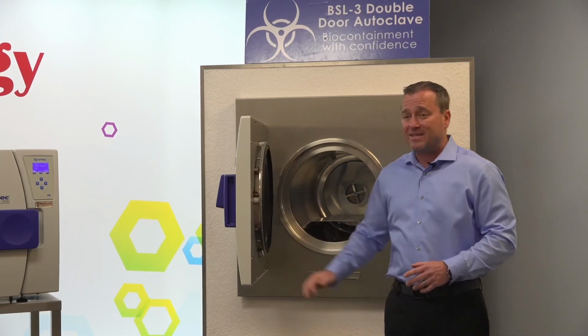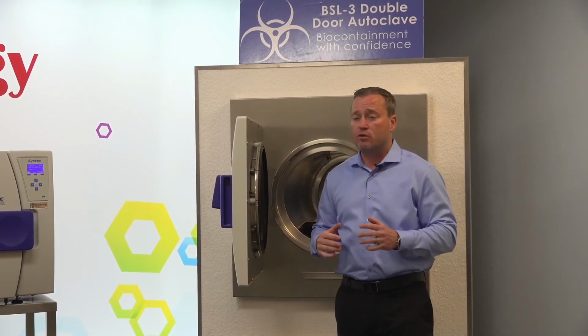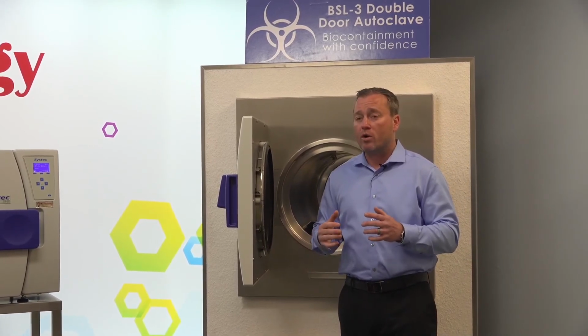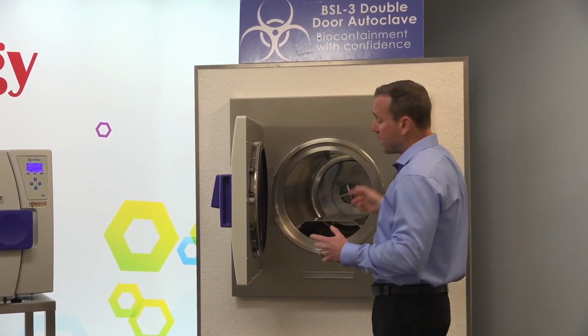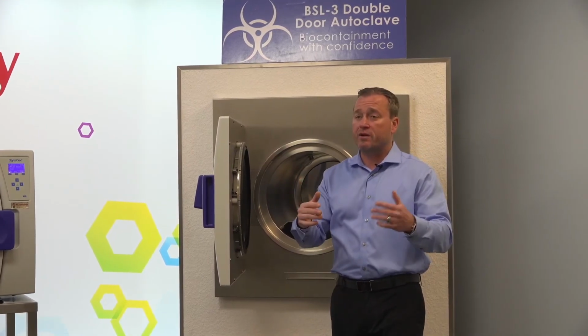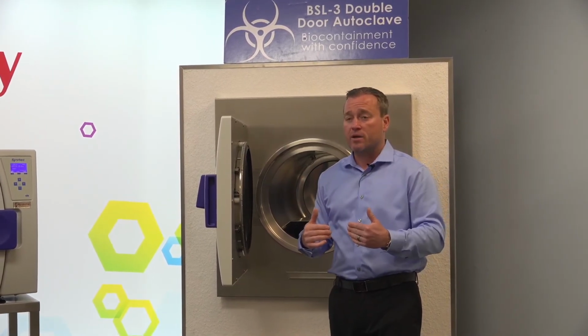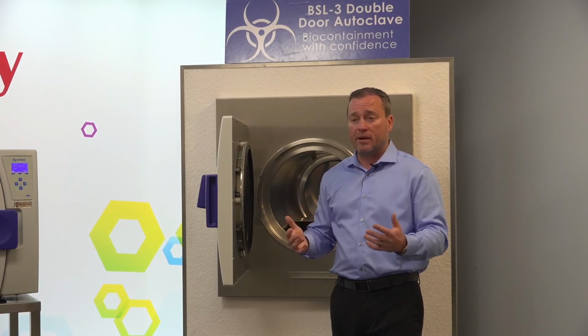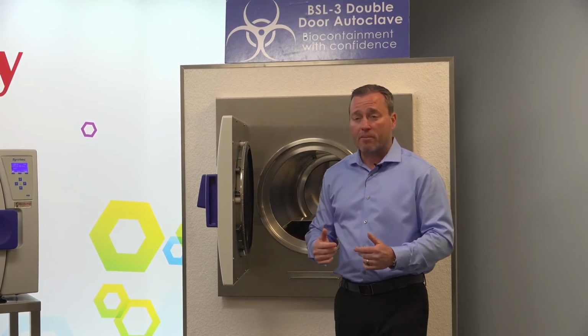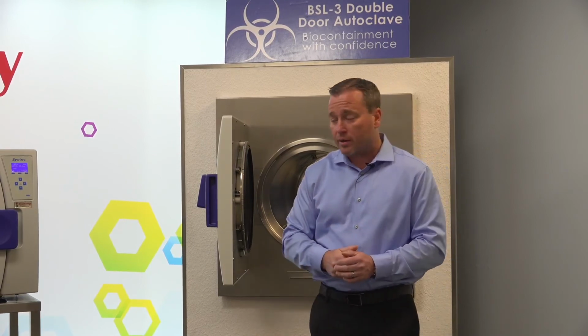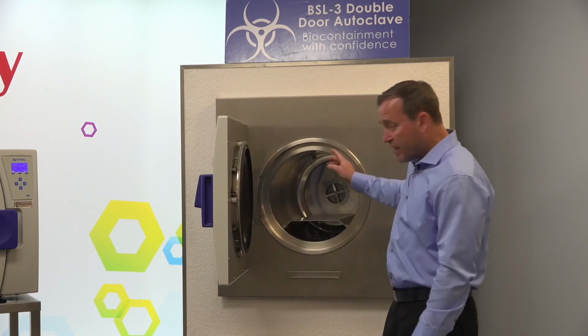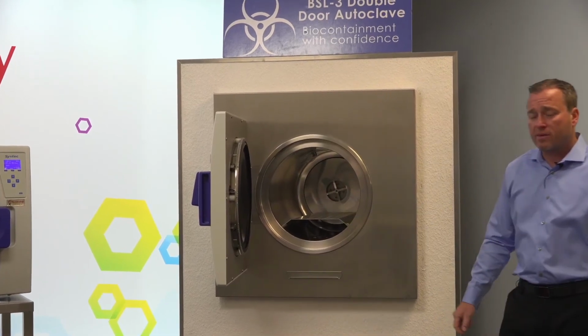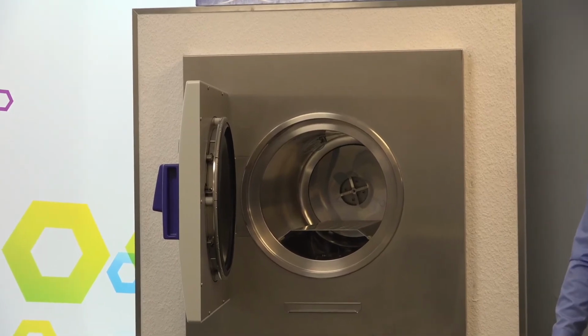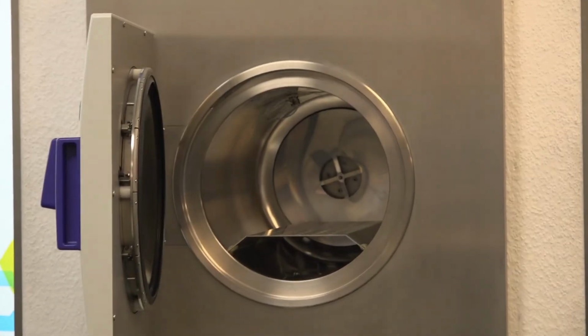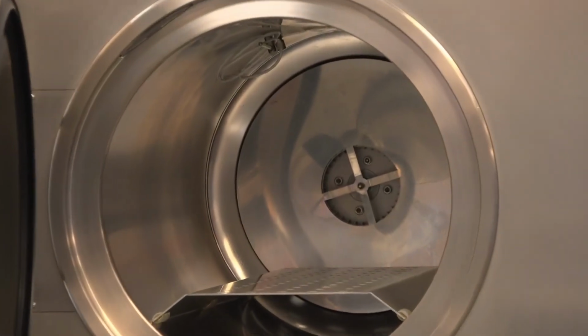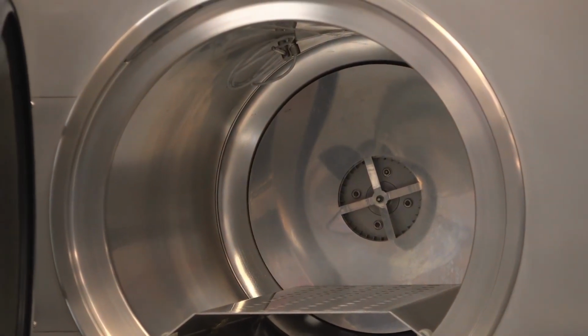These are very easy to integrate. Not a ton of utilities are required. Once you have the hole cut correctly, the instrument just wheels in. We seal both sides of the instrument, and then you have an ability to smoke test the laboratory and get it up and running. So the radial ventilator in this unit is sitting all the way at the back. It's on the back door of the instrument, so I'd just like to get zoomed into that to show you. So that is a radial ventilator option as well.